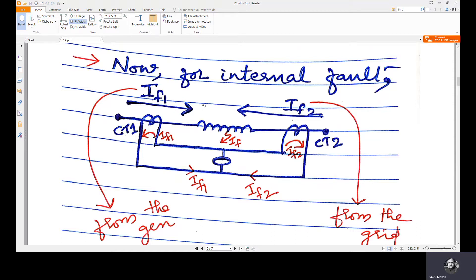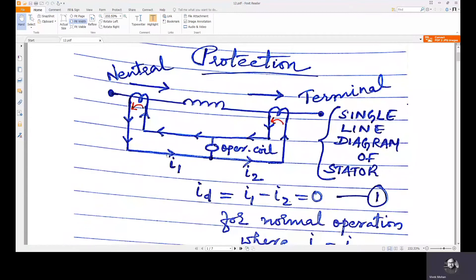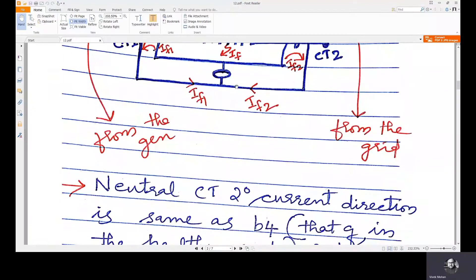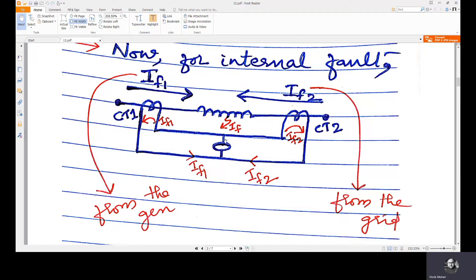Accordingly, the secondary current of CT2 is changed because the primary current is changed. The direction of IF1 follows the earlier direction, but IF2 is reversed. So now we have the differential coil current ID equals IF1 plus IF2. There is a differential coil current when there is an internal fault, and if the sensed magnitude of ID is greater than the ID setting, then the relay will issue a trip signal to the circuit breaker to isolate the generator and clear the fault.